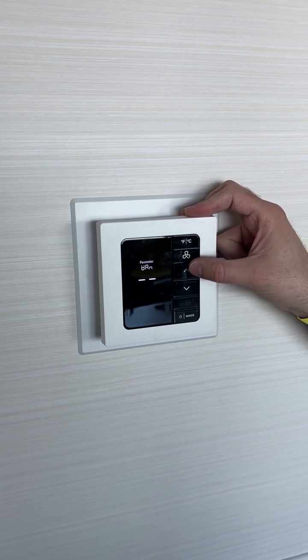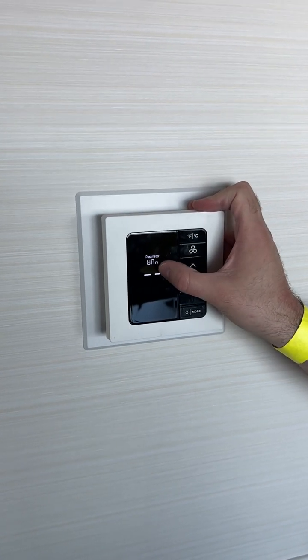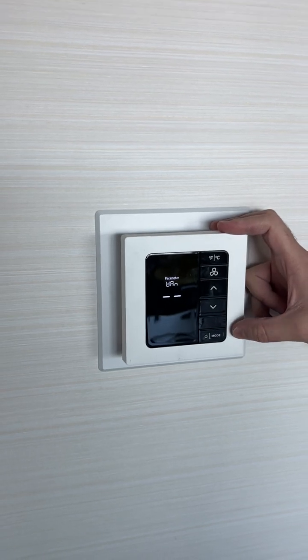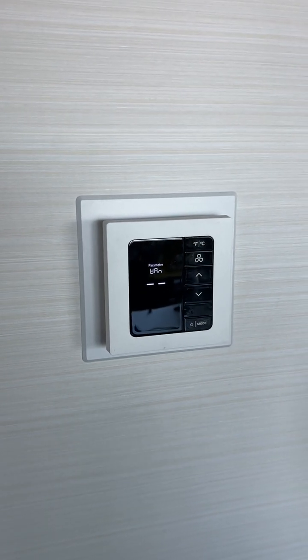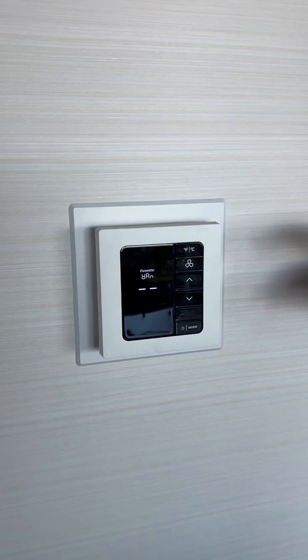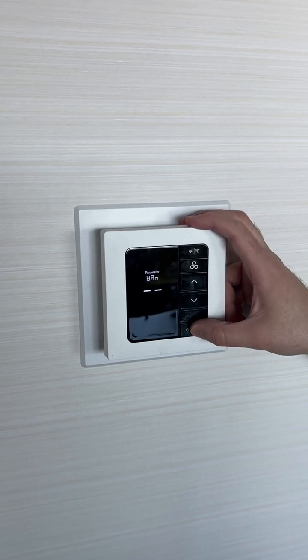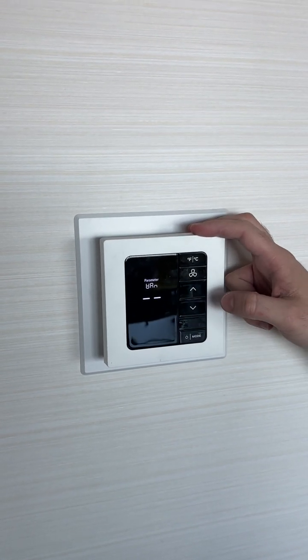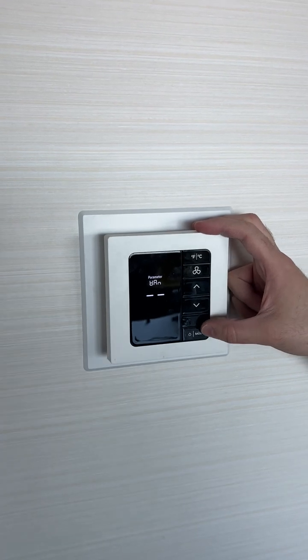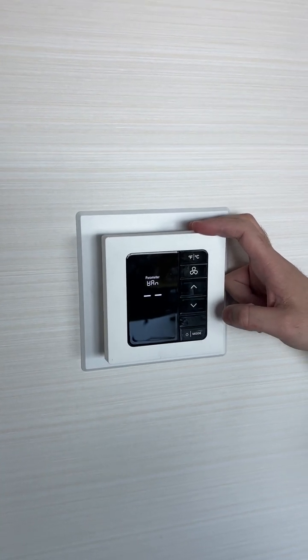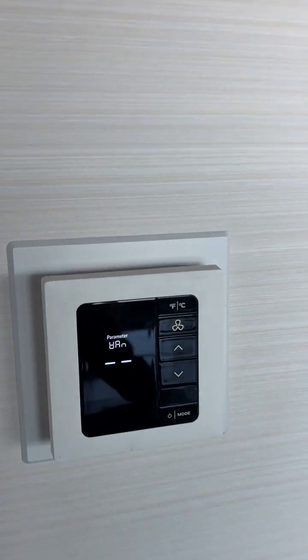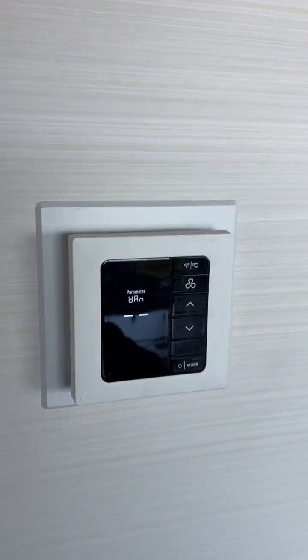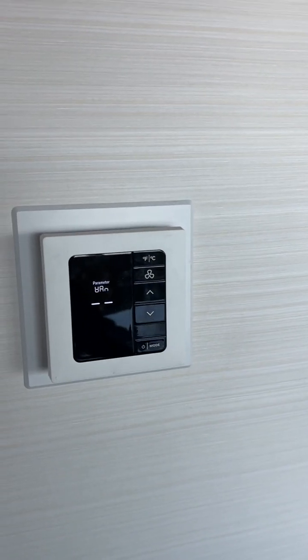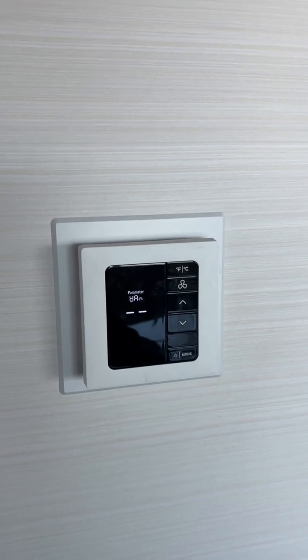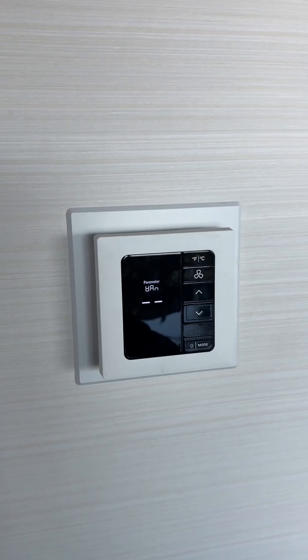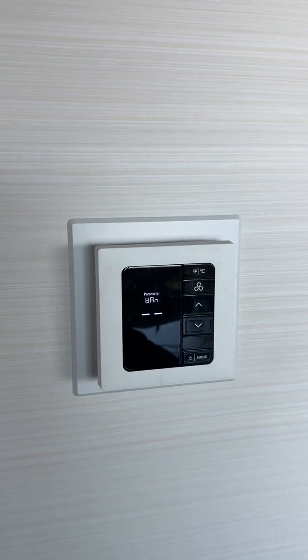Just getting FC to back out. Upside down AAN, or WAN, is a server test. Currently the server isn't communicating with the rooms, so it's going to fail the test, so we press mode, and it just says DON. If it was communicating, we'd see the room number flash across the screen too. That's us asking, hey, what's my room number? The done message just means, hey, I sent that. So if we don't receive the room number back, it's not communicating with the server.